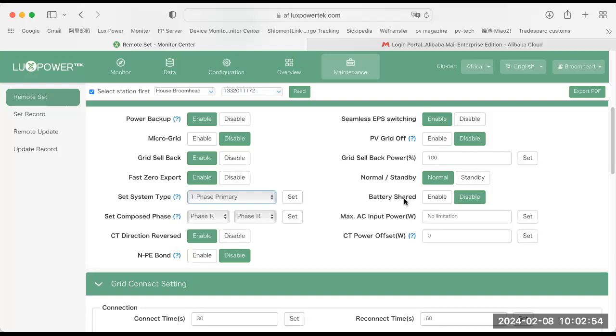And especially when you do your parallel correctly, it means that the master will control the charging of the battery. So in other words, it might assign itself as the charger, or it might assign the slave as a charger, or it might even assign 2 slaves to charge. It's very uneven, but it does control the charging. Here you can also set the composed phase. This is for your 3-phase installations.